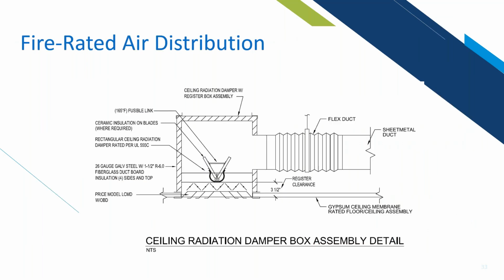Along those lines of fire rated air distribution, we have a really great detail at Buckley that we can use on any of your projects that are involving wood frame construction. It's really important to understand that when you are designing a space, you can't use a standard diffuser and put a thermal blanket over top of the back of the diffuser and then have a CRD in the neck. That will not be a UL compliant assembly.